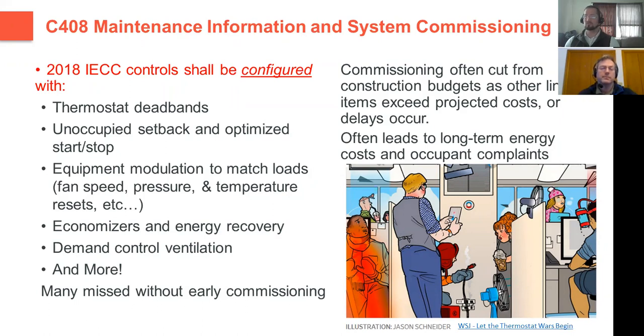If any of those aren't working properly, it can result in a lot of excess energy consumption for the building, or discomfort for the occupants, who then go and try to tweak the thermostat settings or change other things. If these aren't working right, it's a lot of extra workload on the maintenance operators. Unfortunately, what we see a lot of times with construction, since commissioning happens at the end of the project, right before turnover to the owner, a lot of times with tight budgets or tight timelines, commissioning gets reduced or removed from the budget and doesn't get completed properly. And so it leads to a lot of long-term problems. And you can kind of see in the image here, the guy's hot in one corner, someone else is cold, someone else has got a fan blowing on them, people are fighting over the thermostat settings.